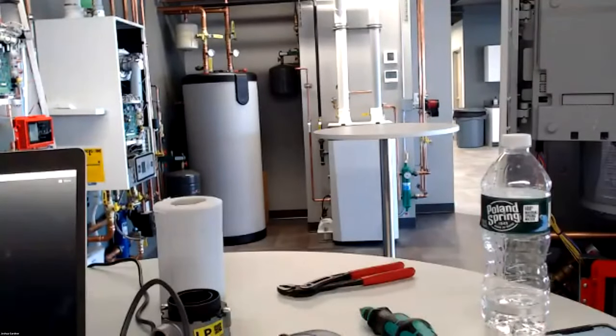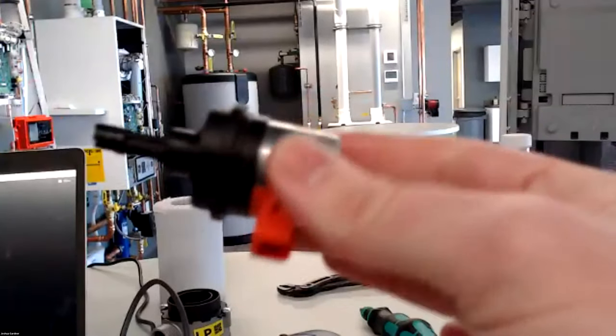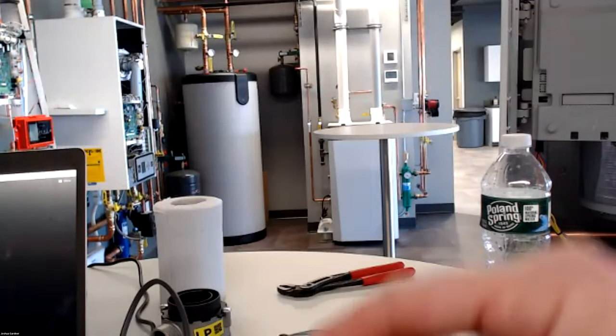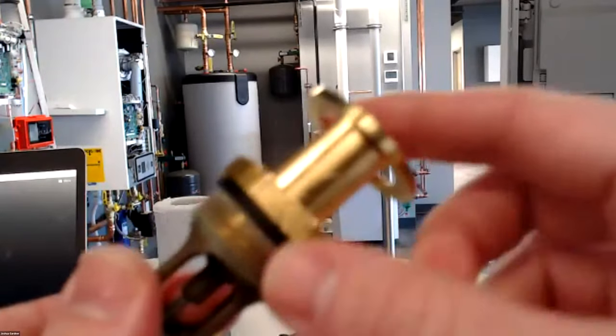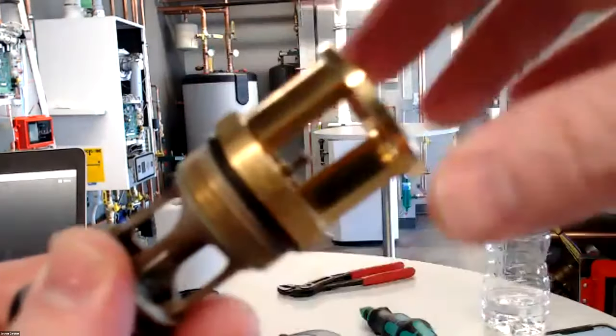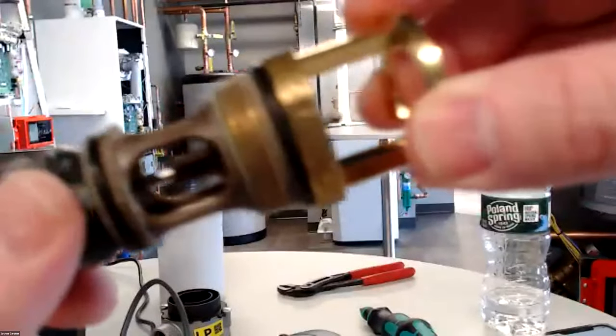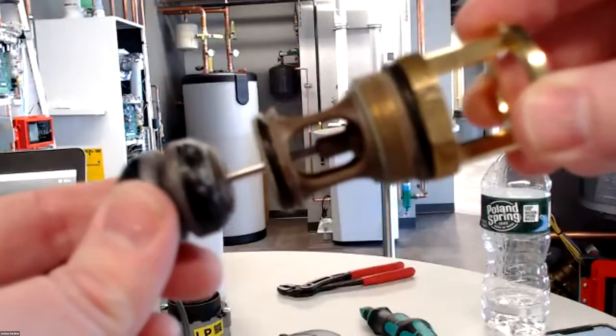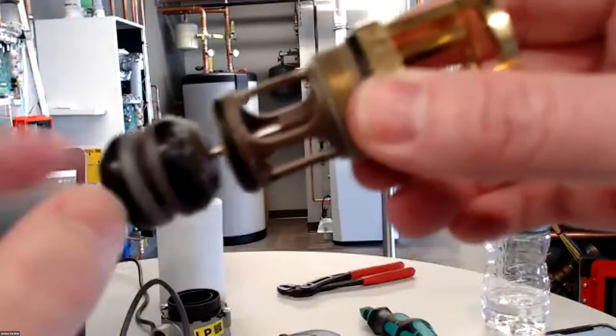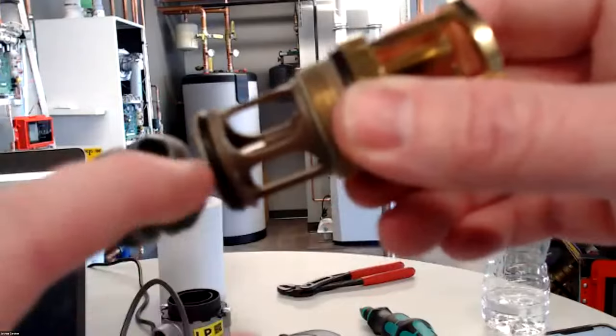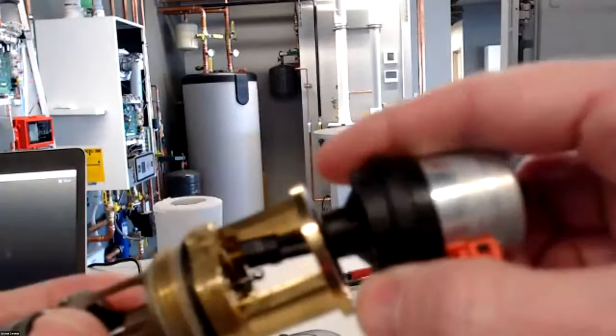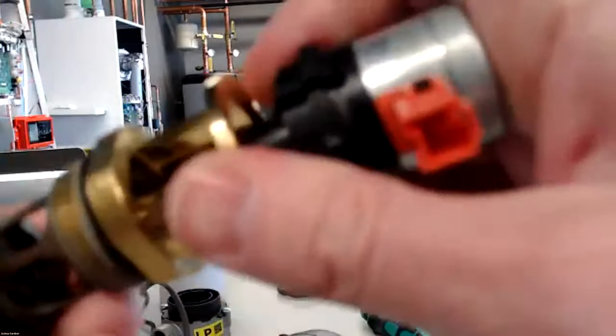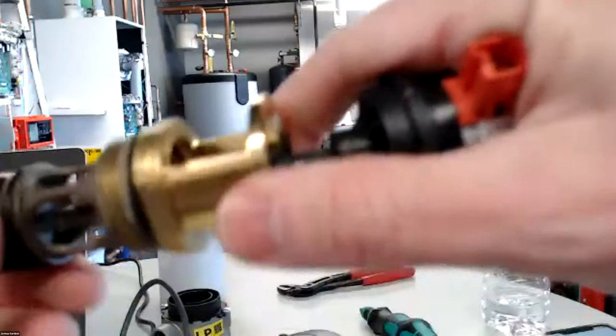Okay. So going back where we dropped off, the three-way valve or diverting valve. Again, this is your solenoid. This is the wet connection. This part right here, brass body, will be threaded into the main body, gasket right here. And this guy will just move up and down and divert that water. One thing to note we've seen is debris from construction getting caught up in here and causing resistance, and then this solenoid pulling away and breaking from the plunger.